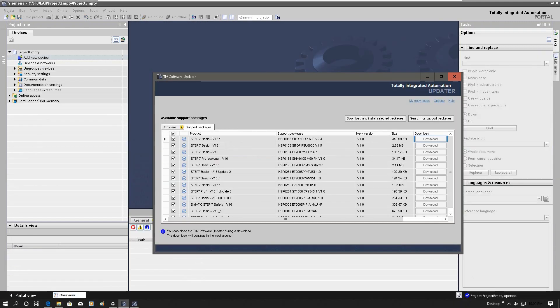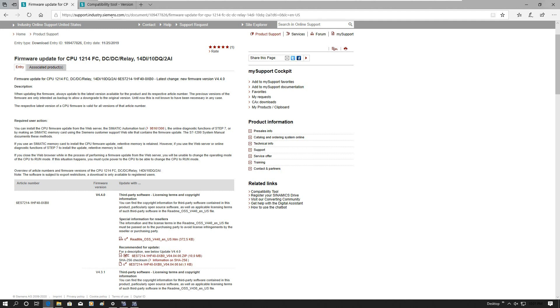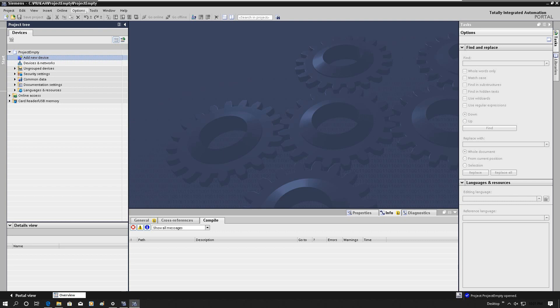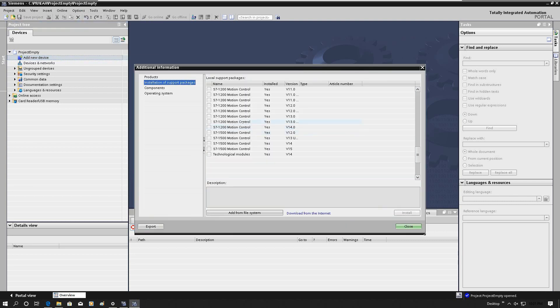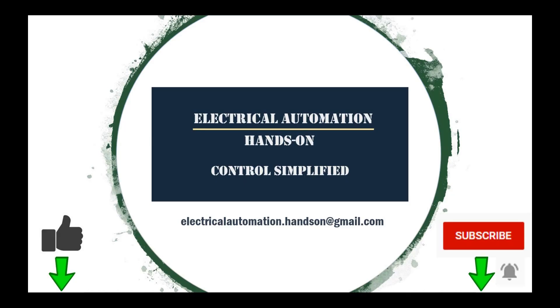So that is it for today. We have two ways to upgrade TIA Portal: the first is to go online and use the TIA Updater to download everything automatically — that is the easiest way. The second is to go to support.industry.siemens.com and manually download the update, service pack, and HSP hardware catalog files. For HSP, remember to go to Options > Support Packages > Add from File System, load the files, and hit Install. Thank you for watching — if you like this video, please give a thumbs up and subscribe to see more videos.